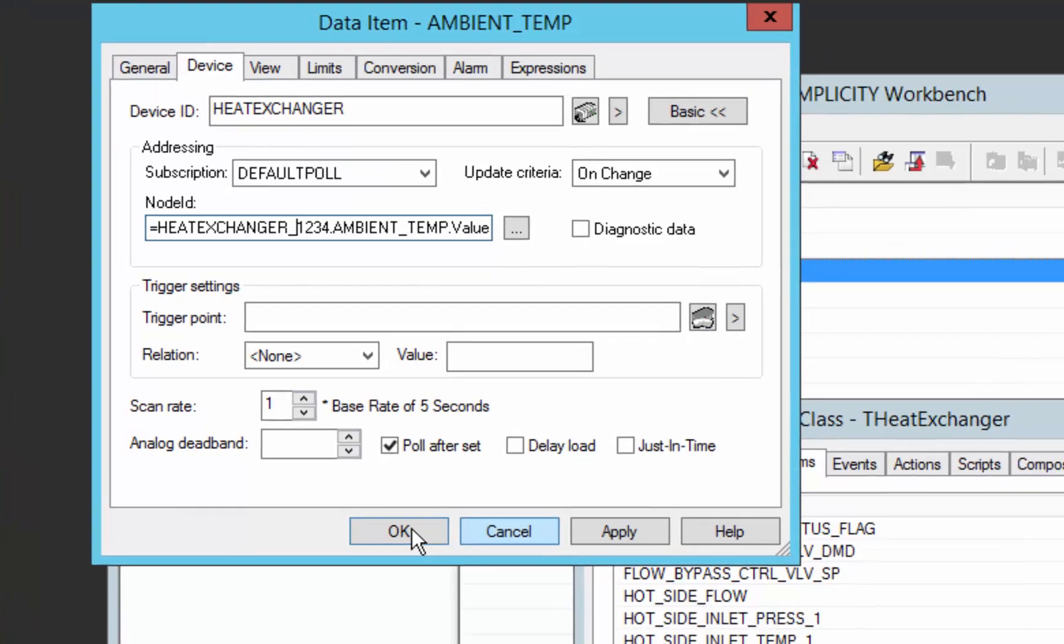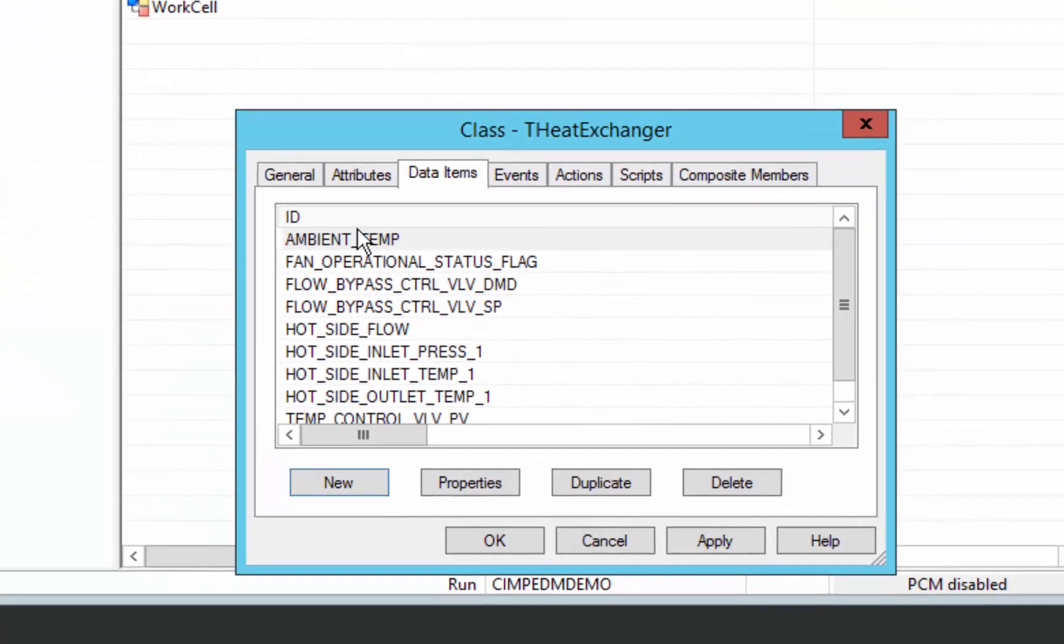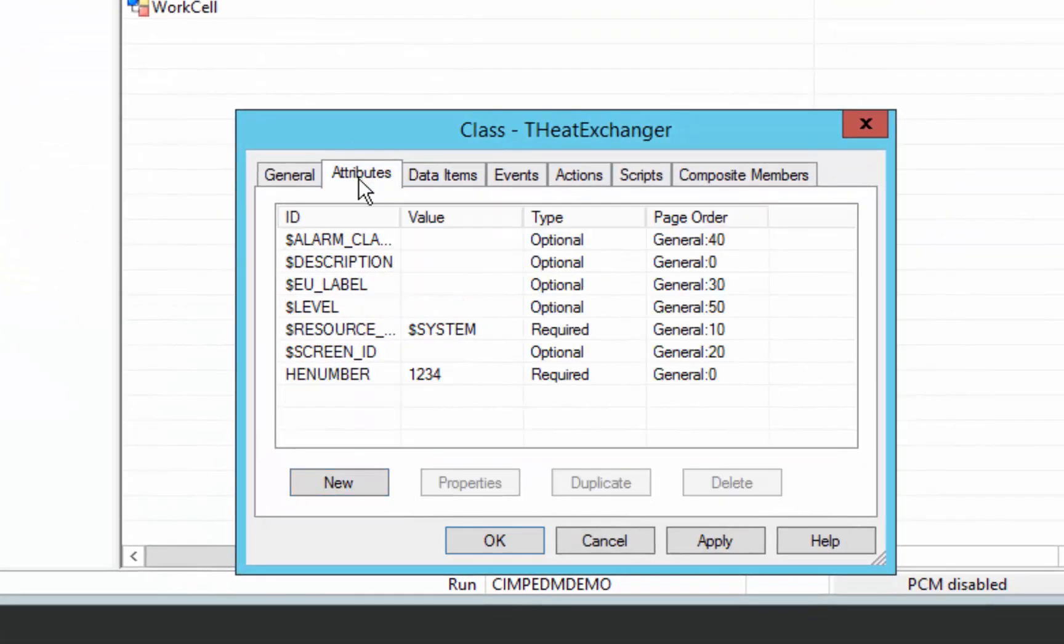since there's two heat exchangers, we want to reuse this class and create an instance of heat exchanger 1234 and another instance of heat exchanger 2345. But we don't want to have to modify the address of the points we're retrieving for each specific instance. So we're going to use the concept of attributes.